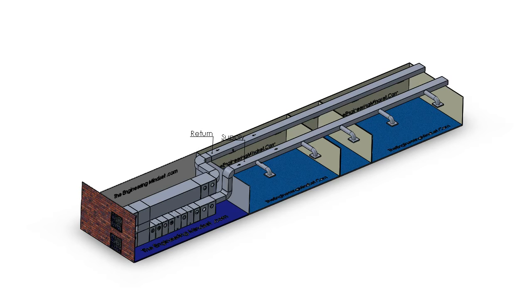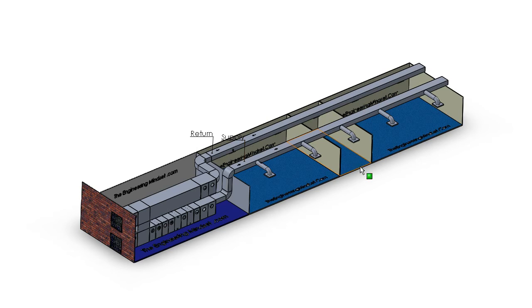One of the problems with the CAV system is that everything connected to this AHU is classed as one zone, meaning all the rooms connected to it receive the same temperature air regardless of their heat load. So if this room here was a busy meeting room in the middle of summer, full of people generating a lot of heat with solar thermal gain, it would receive the same air temperature as a little room with just one person in it — which is going to be very uncomfortable. This means the zones are not receiving their required cooling, so the system is not efficient because it's wasting cooling energy providing cooling to a room that doesn't need it.